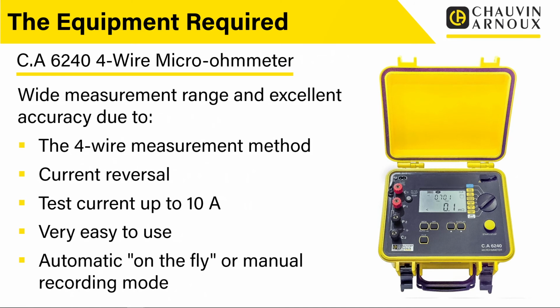Really easy to use. You can see on here it's just a turning knob to select the range, and then basically a start-stop button to do the tests. So really simple. But it's also got some great features like the automatic on the fly or manual recording mode. So again, you can connect it up, set it going, and whenever you make a connection, it will automatically store that result, and you can save your results and then download them to the software afterwards.